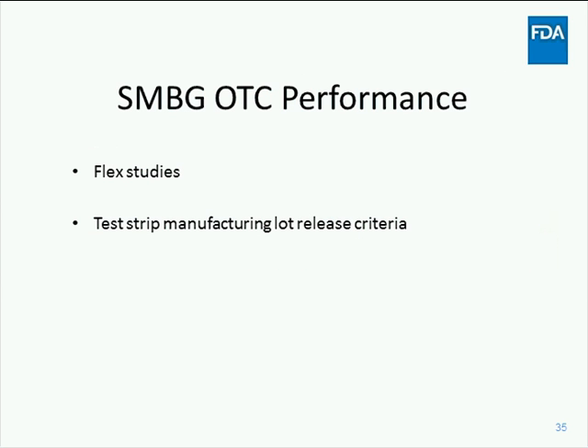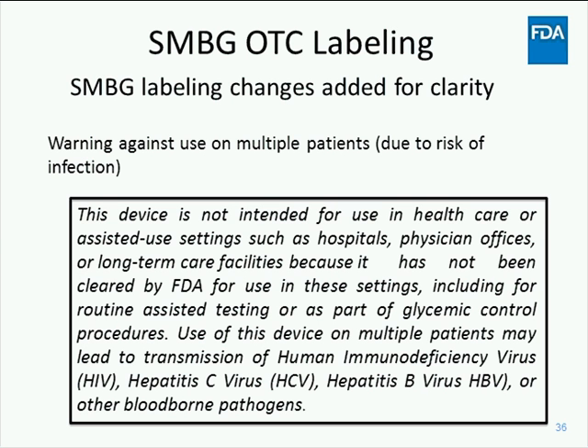The SMBG guidance recommends similar flex studies to those described in the BGM guidance, and also recommends that the test strip manufacturing lot release criteria be provided for the over-the-counter systems. For SMBG devices, the following warning should be included prominently on the outer box label and package insert for SMBG systems. This warning emphasizes that the system is not intended for use in healthcare or assisted use settings such as hospitals, physician offices, or long-term care facilities, since it has not been cleared for these uses, and the use on multiple patients could lead to the transmission of bloodborne pathogens such as hepatitis B.